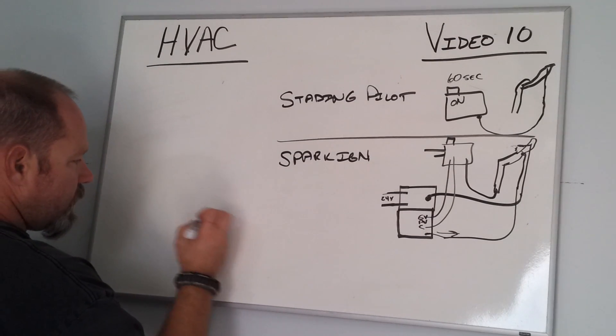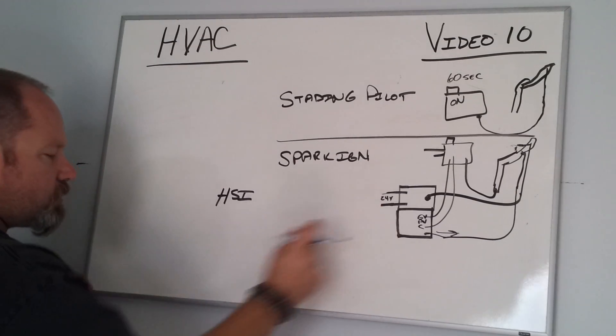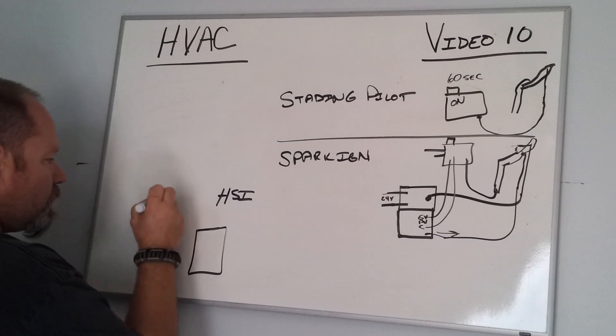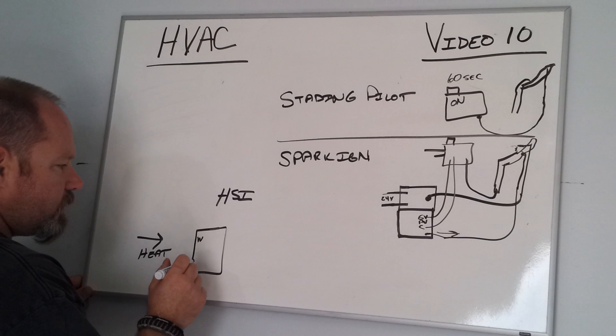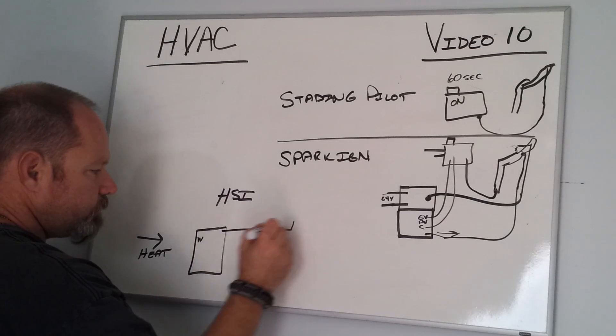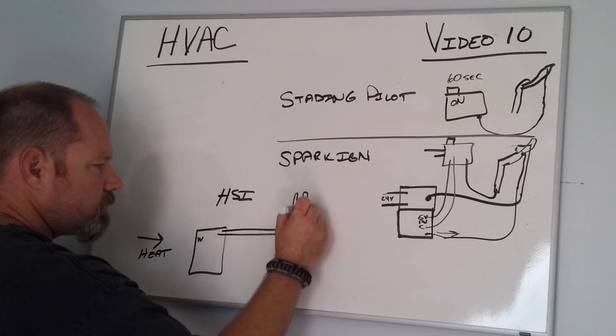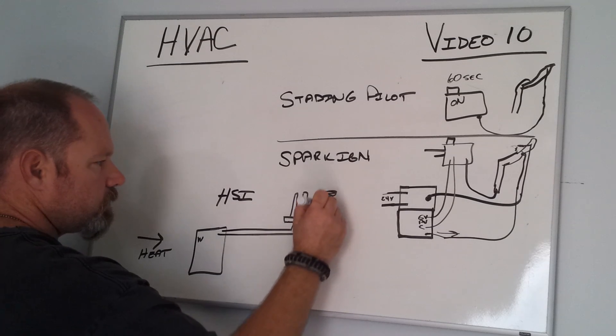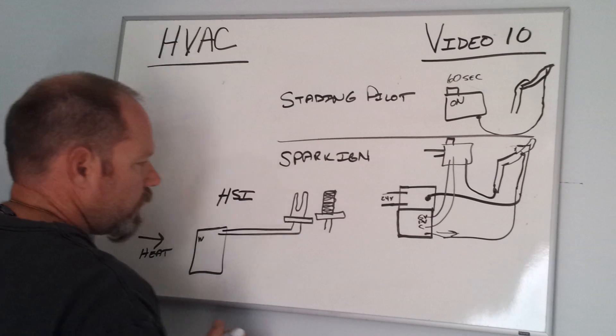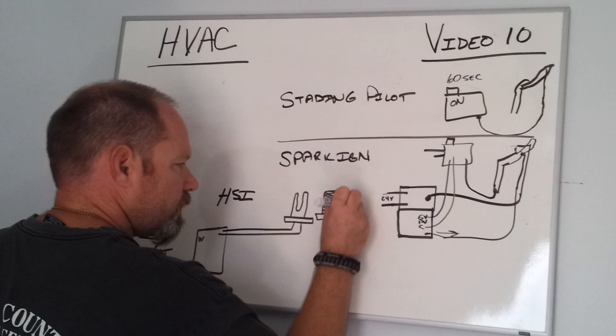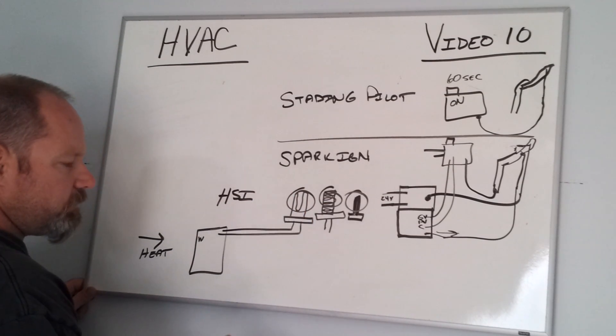The newest style is HSI — hot surface ignition. Hot surface ignition also uses a control module. When you get a call for heat on W, the hot surface ignition sends power to one of several different style electrodes. There are a few different designs, but the most common ones include a coil-style and a flat card style that looks like a bar. This area glows red hot and is located in front of the manifold somewhere.